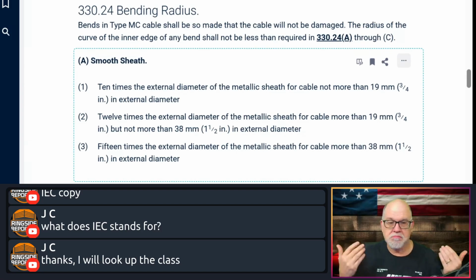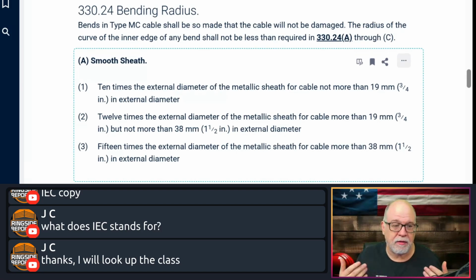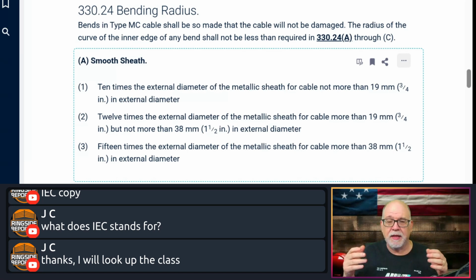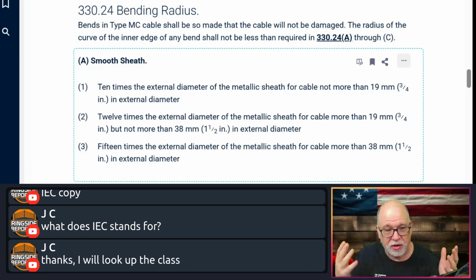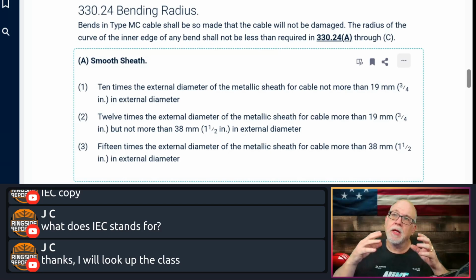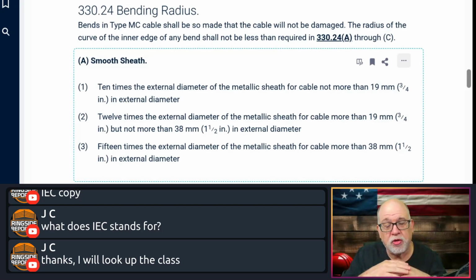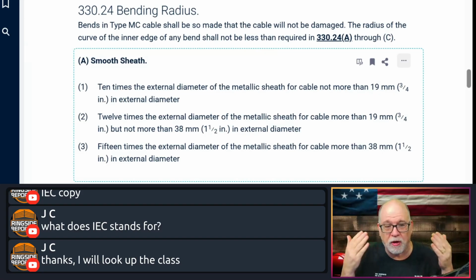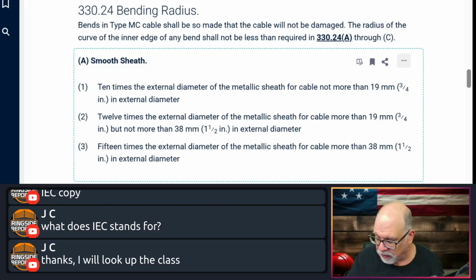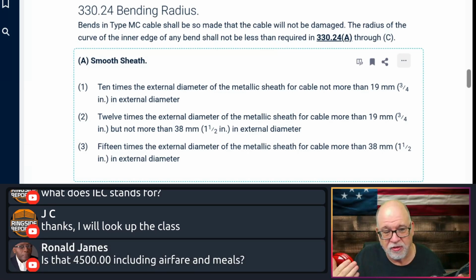We cannot give you a way to fix a damaged MC. Now you can get creative. You can put jumpers on it. Remember, it's just bonding. Even though it broke apart, the strip is still connected, so it's still bonded. You can do whatever you want to do to it, but remember, you own it. Don't expect the manufacturer to fix your mistake. I have a problem if people do that. They want the manufacturer to fix everybody else's installation issues.